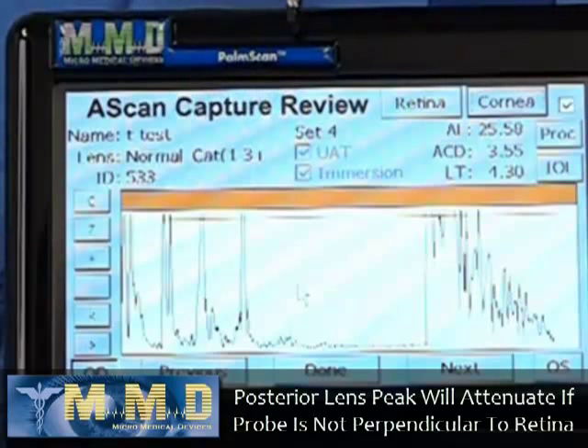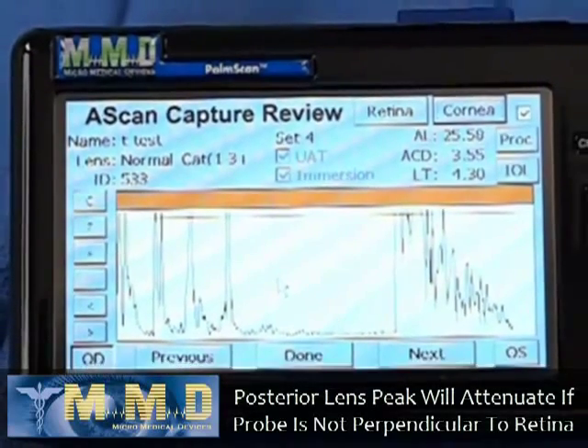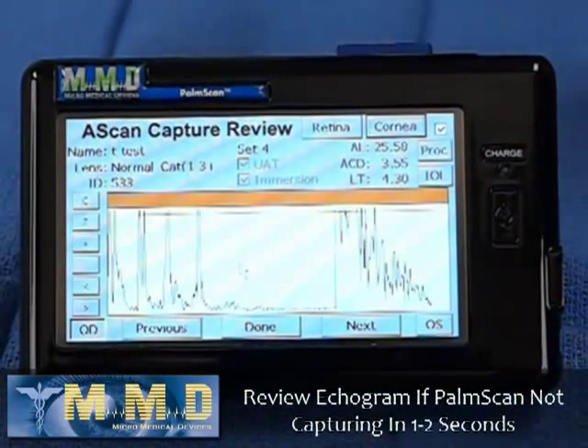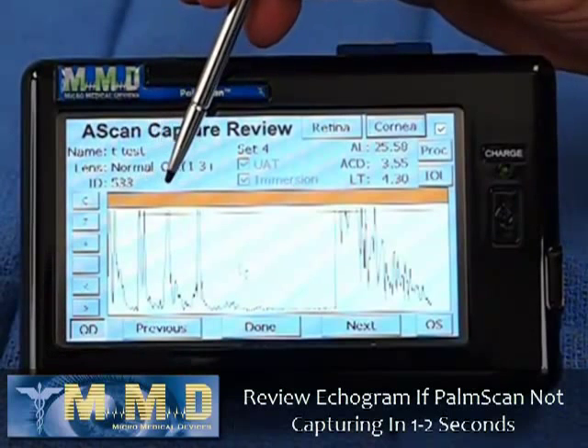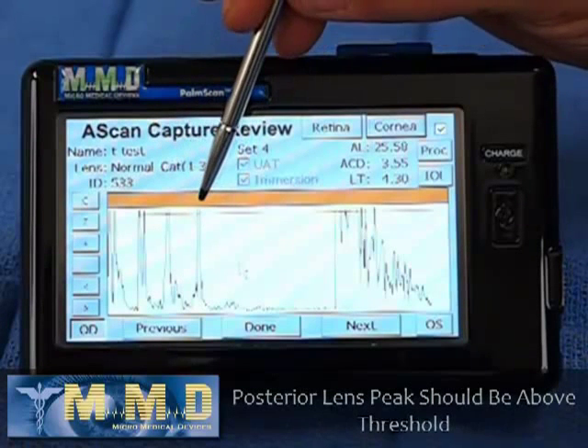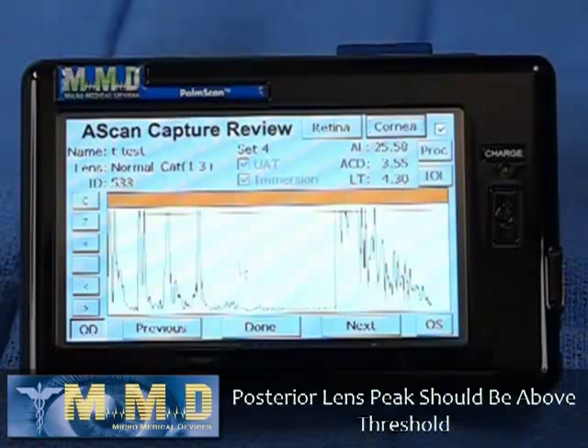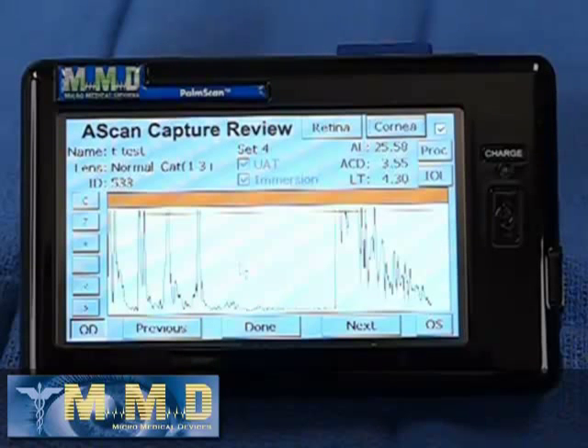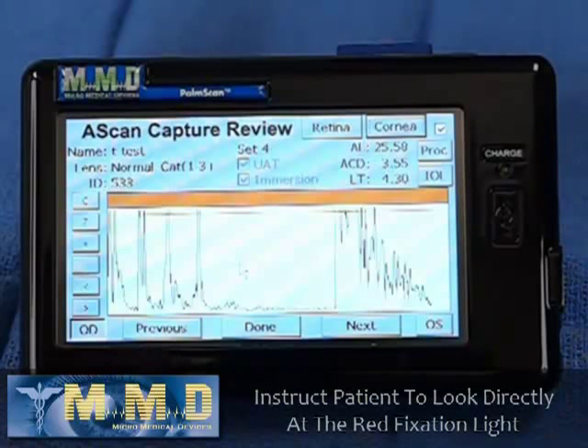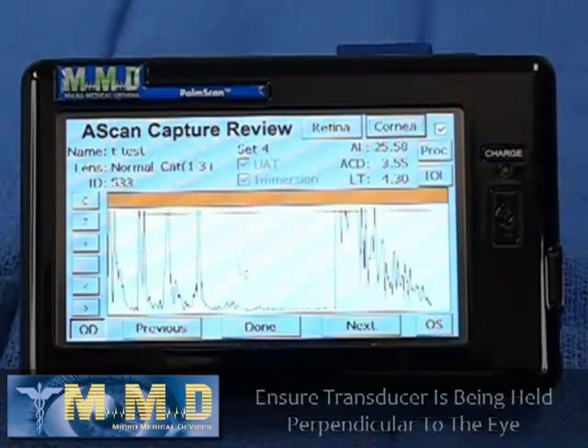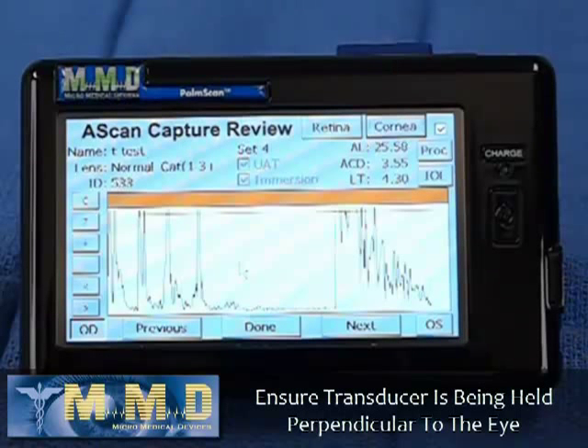So if you place the PalmScan on the eye and it's not capturing after 1 or 2 seconds, we recommend that you look at the echograms and make sure that the posterior lens spike is above threshold. To do that, you might just have to realign your transducer in relationship to the patient by instructing them to look directly at the blinking LED, and also make sure that you're holding the transducer perpendicular to the eye and not at an angle that prohibits the eye from being perpendicular to the transducer.